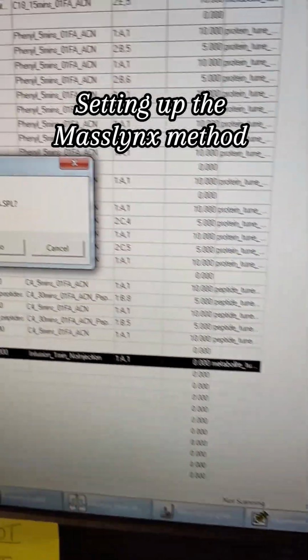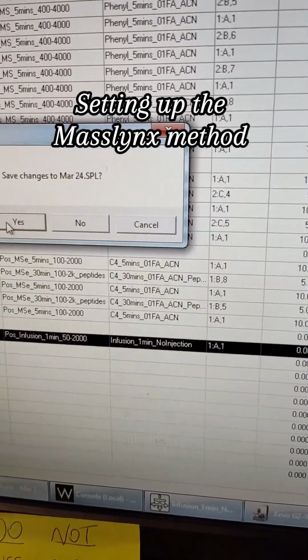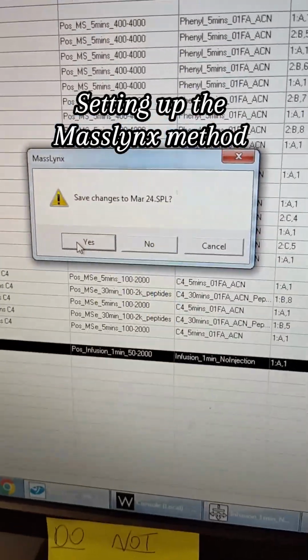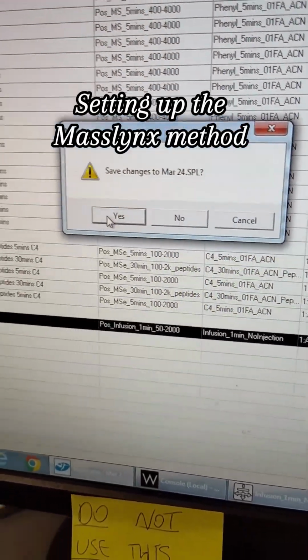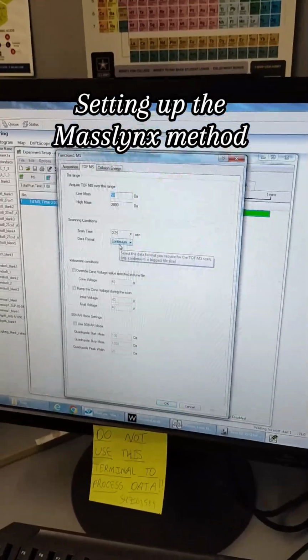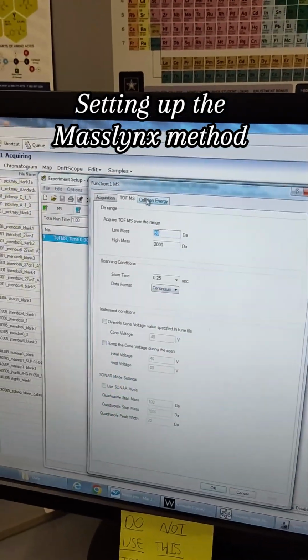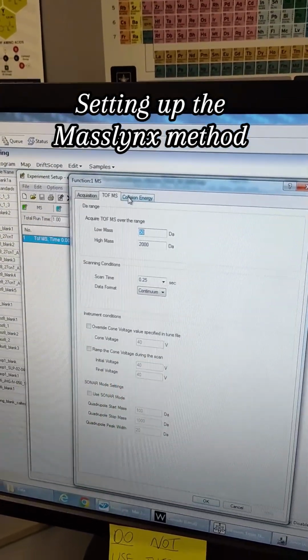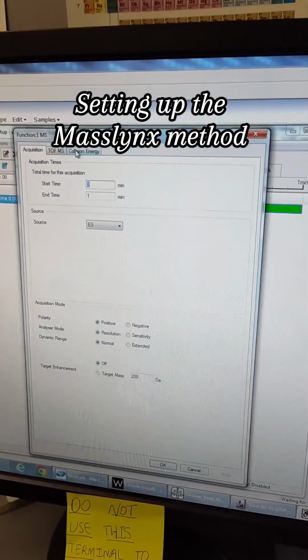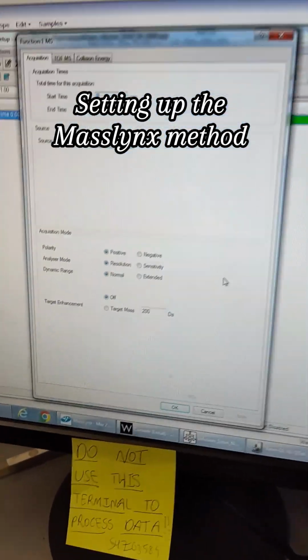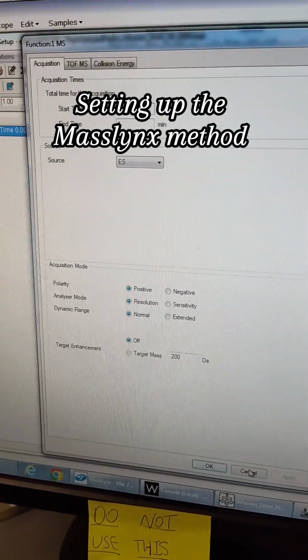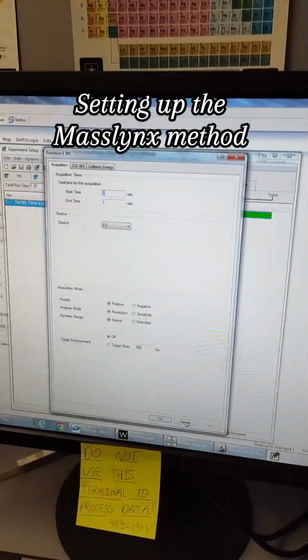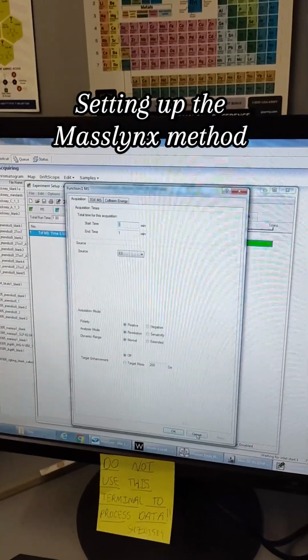You have the method called up with a 0 volume injection with the metabolite tune that we want to calibrate. This is a 1 minute no injection infusion run with the combined, and it's positive mode right now, but there's a negative mode one as well. So it's just a continuum mode, MS1, feature only, 50 to 2000 with 0.25 scan. I don't think the scan speed is required to be 0.25, but that's what we've chosen. And we are, again, not doing dynamic range enhanced here. So this is just a regular MS1 continuum file.